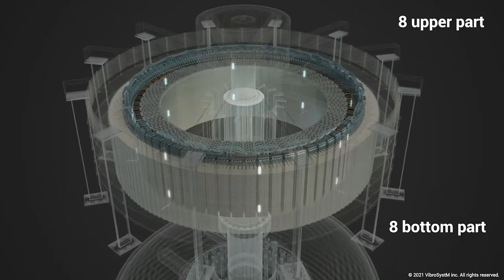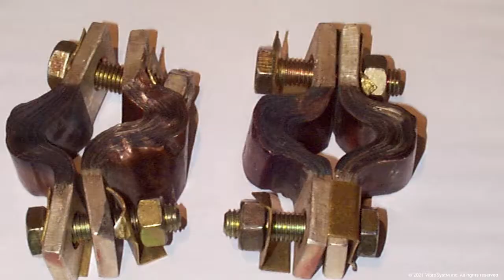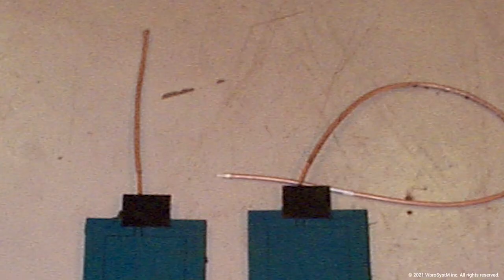And in fact, we could see that some coaxial cables were already ripped off. They were actually clipped by the rotor. In reality, for the cables to be clipped, something needed to be at a distance less than 3 millimeters from the core, because the cables are very small. So in the end, they found some pole interconnections that were actually damaged. So they were very close to hitting the stator core. That was the first indication there was a potential issue with the rotor.